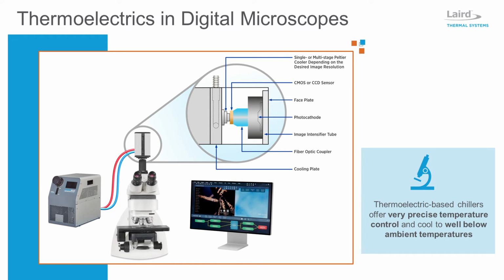Recirculating chillers can also be used in combination with a thermoelectric cooler to reduce thermal noise and ensure maximum image resolution. This illustration shows how heat from the microscope camera is absorbed via a liquid coolant that is circulated by the liquid-to-air heat exchanger in the thermoelectric chiller. The chiller cools the temperature of the coolant circuit while exhausting waste heat into the ambient environment.